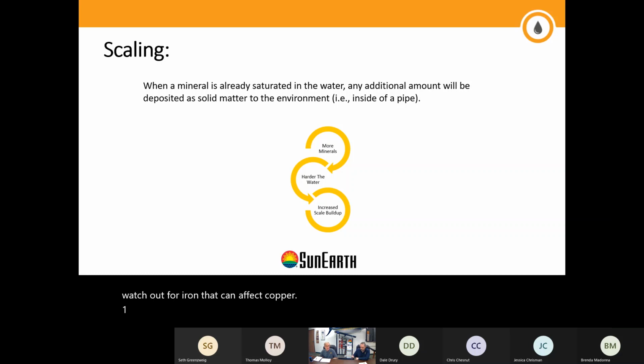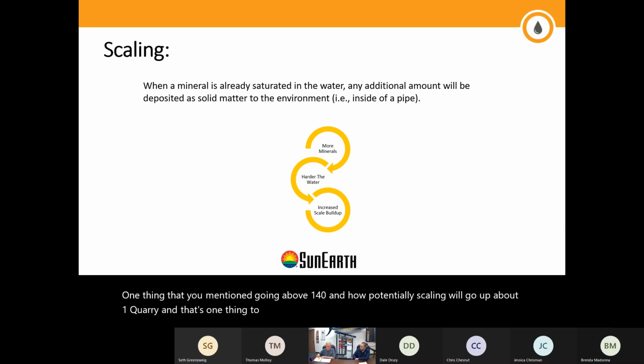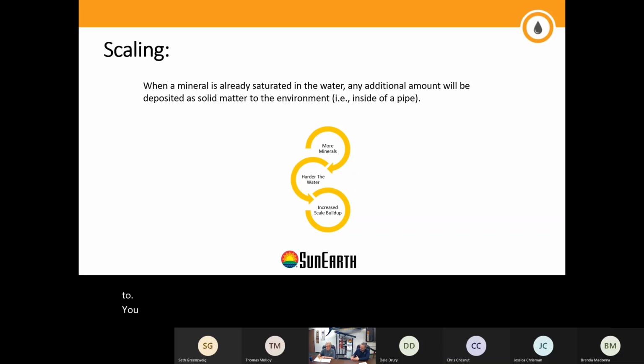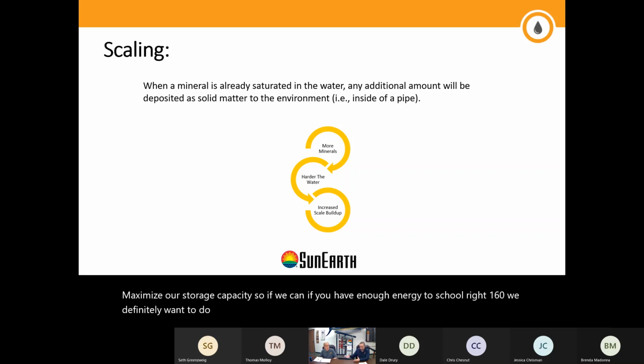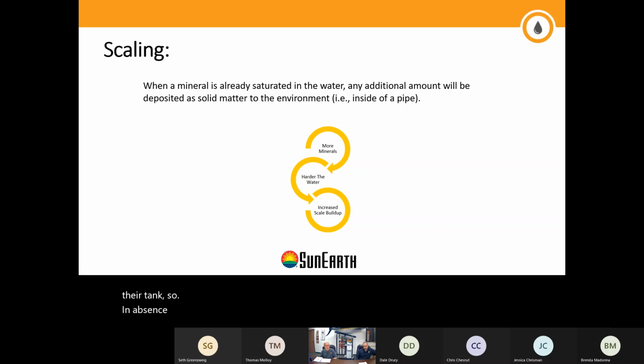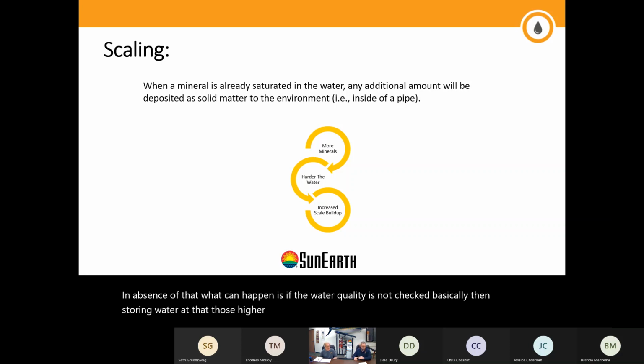One thing you mentioned is going above 140 degrees, and how scaling increases exponentially above that point. That's important to consider, especially with solar thermal, because we try to maximize our storage capacity. If we have enough energy to store at 160 degrees, we want to do that to maximize the footprint of your tank. But without checking water quality, storing water at those higher temperatures can be problematic and lead to more scaling.